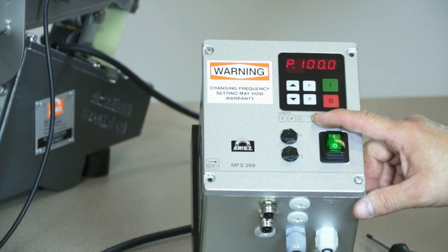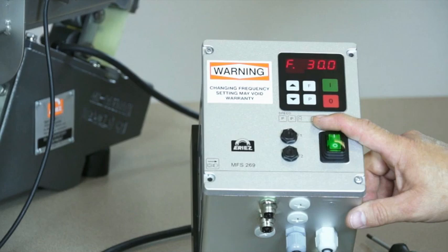This versatile control can be programmed for a variety of frequency settings. Eriez offers several vibratory feeder options that operate at 30, 40, 50, and 60 hertz, and this control can be programmed for use with any of these frequencies. The frequency is easily adjustable through a simple programming procedure. Typically, the control output frequency is set at the factory to match the input frequency of the vibratory feeder before shipment. For more information on frequency adjustment, please see the G-Series control setup video.